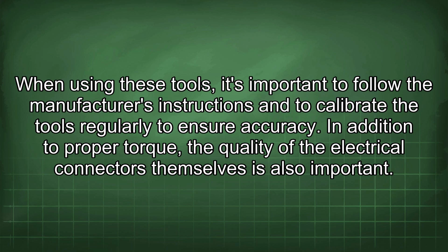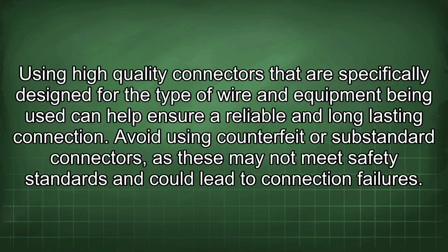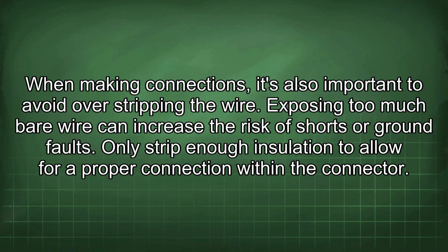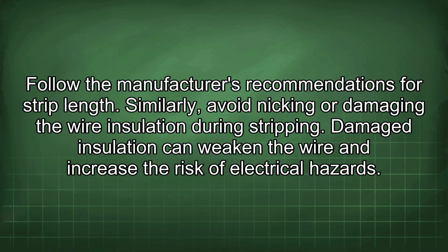In addition to proper torque, the quality of the electrical connectors themselves is also important. Using high-quality connectors that are specifically designed for the type of wire and equipment being used can help ensure a reliable and long-lasting connection. Avoid using counterfeit or substandard connectors, as these may not meet safety standards and could lead to connection failures. When making connections, it's also important to avoid overstripping the wire. Exposing too much bare wire can increase the risk of shorts or ground faults. Only strip enough insulation to allow for a proper connection within the connector. Follow the manufacturer's recommendations for strip length.